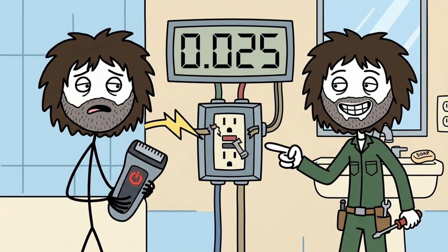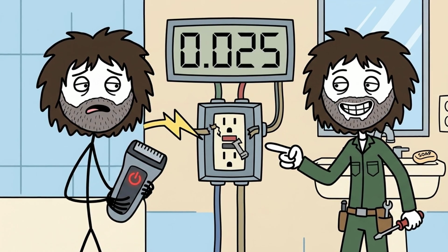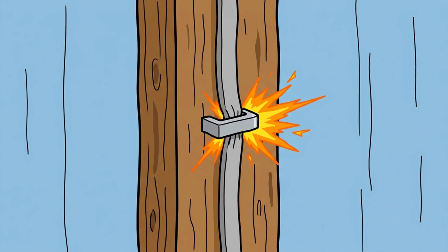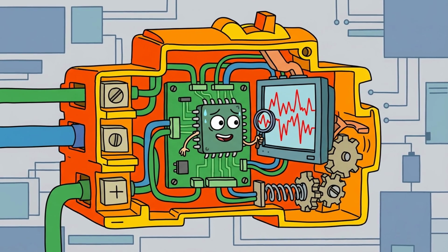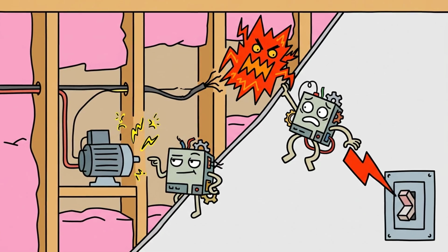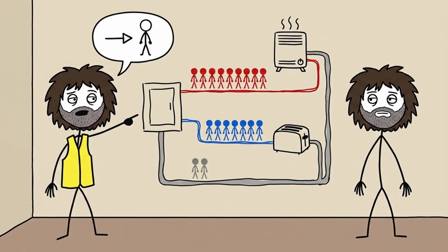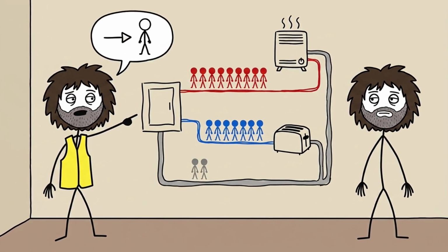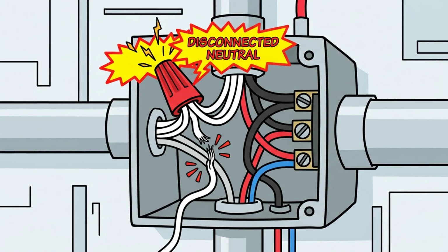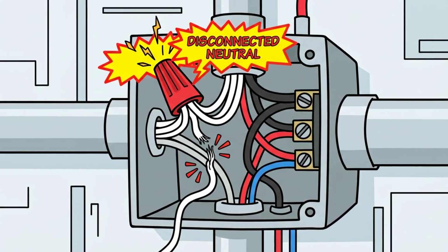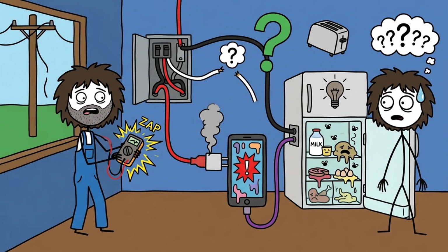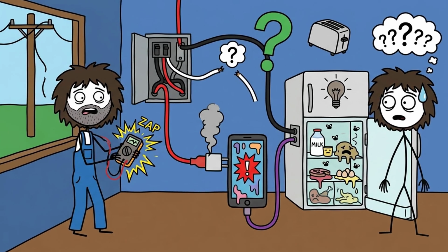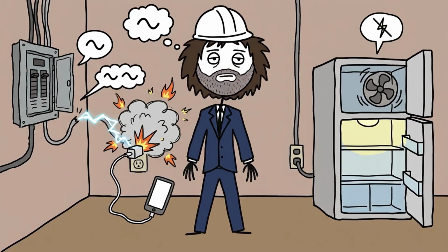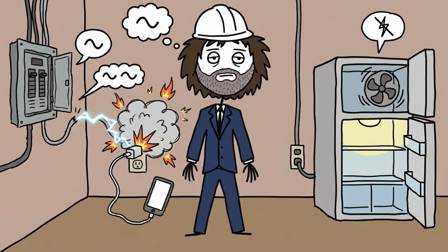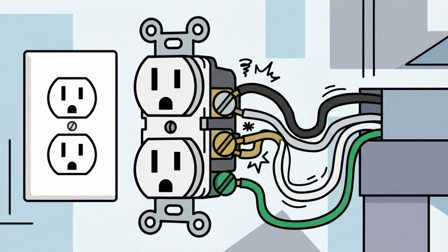Another hazard is reverse polarity combined with loose neutral connections. If an outlet is wired backwards, hot wire to silver and neutral to brass, appliances function normally. However, internal switching contacts inside lamps now sit on neutral. This leaves light bulb sockets permanently energized at 120 volts even when switched off, creating an immediate shock hazard for anyone servicing the appliance.